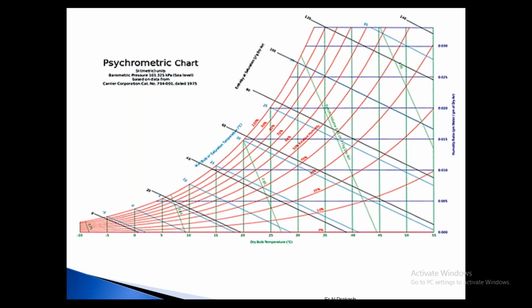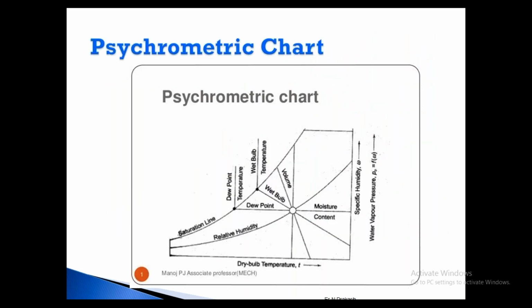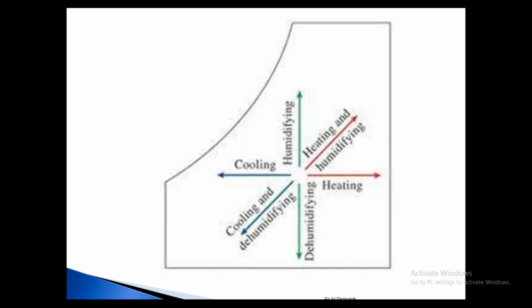In the psychrometric chart, if you know two parameters, the other things you can easily find out. If you just buy a whirling hygrometer, a dry and wet bulb hygrometer, and check the dry bulb temperature and wet bulb temperature, you can mark them in the chart and find out the moisture content in that air. That plays an important role for quality and everything. The plant will be operated based on humidification, that is psychrometric principles. There are 8 basic psychrometric principles. Heating: when the outside temperature in winter is low, you have to maintain a minimum of 32 degrees, whereas outside it could be 7 to 8 degrees. So you have to generate heat in the factory to maintain the temperature.